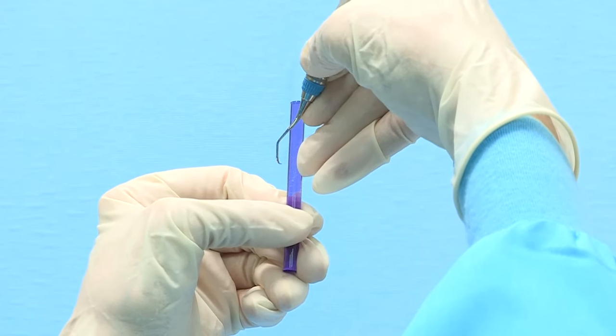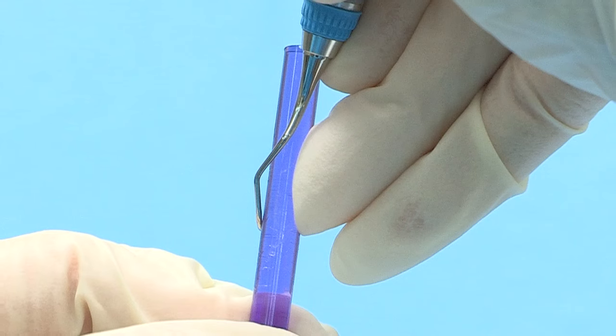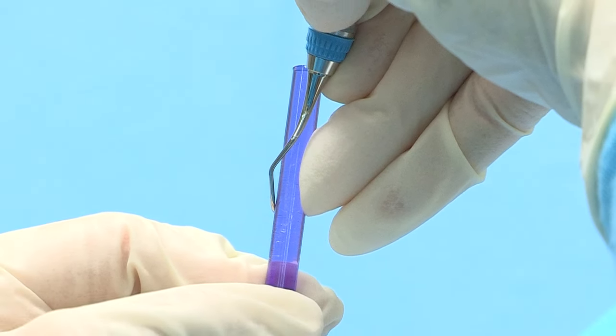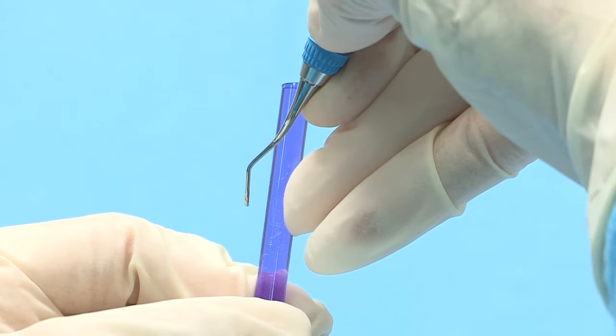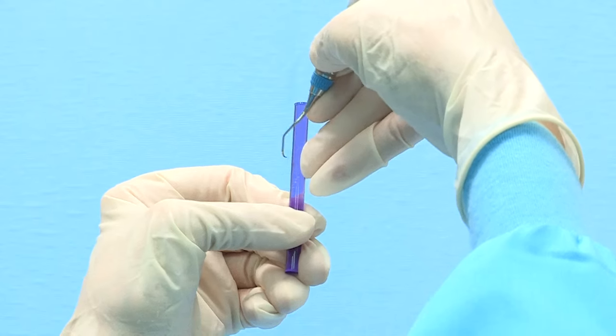Place the cutting edge against the left side of the stick. Place your ring finger against the side of the test stick opposite the cutting edge to act as a fulcrum while testing. Press the cutting edge into the test stick and release. If the instrument is sharp, it will bite or grab the test stick. You will also hear a metallic sound or ping when the instrument is removed. Be sure to test the entire length of the blade.